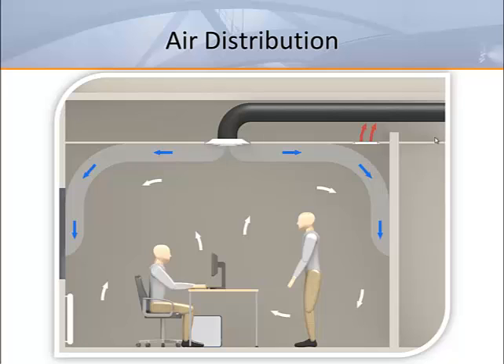Conventional overhead systems provide comfort through room air mixing. For this reason, these systems are also known as fully mixed systems. In a typical application, 55-degree air is supplied from ceiling diffusers or high sidewall grills. The mixing is created by outlet discharge jets resulting in room air motion. This so-called secondary air motion is due to the entrainment of room air into the supply jet where mixing occurs. Ideally, an overhead system results in fully mixed air throughout the space with minimal temperature stratification.